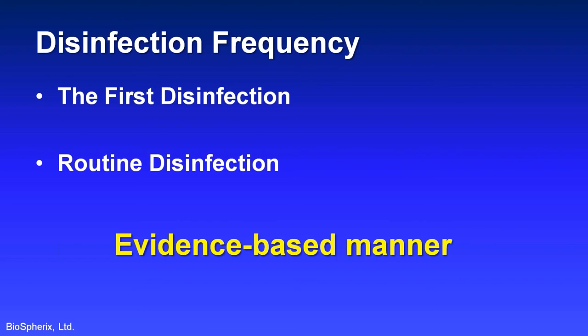As I mentioned previously, frequency of disinfection can help manage risk to cells and tissues in a closed system, or add to it. The only thing that happens inside the Xvivo between the after-use disinfection one day and the before-use disinfection the next day is that the atmosphere is continuously HEPA filtered by the CRAC, cleaner and cleaner. So re-disinfecting the system the next day before use may not reduce the risk to the cells any further, but just introduce more humidity and risk to the systems.